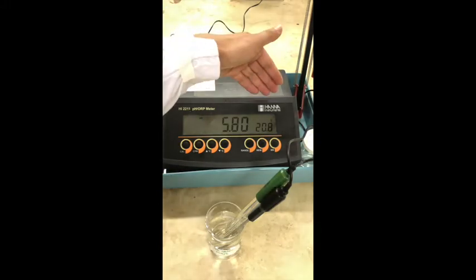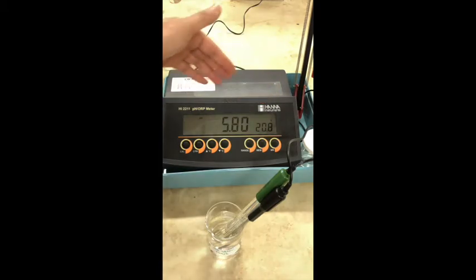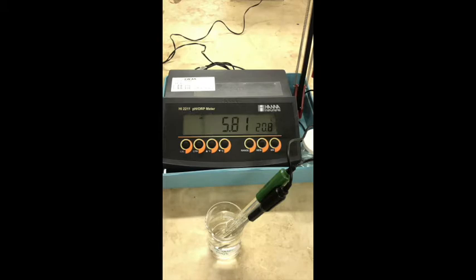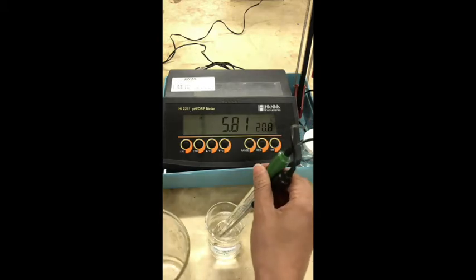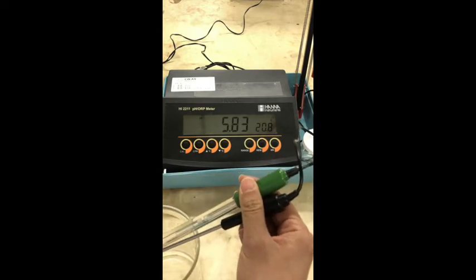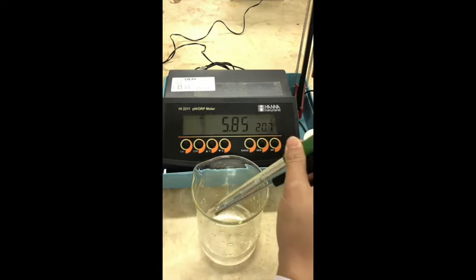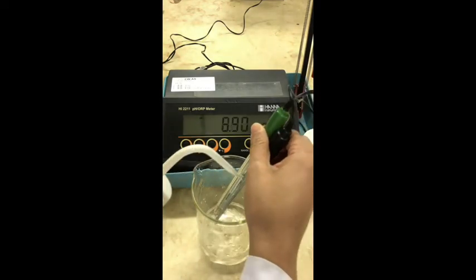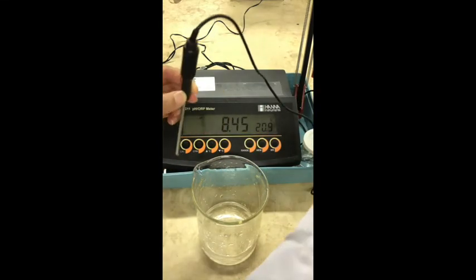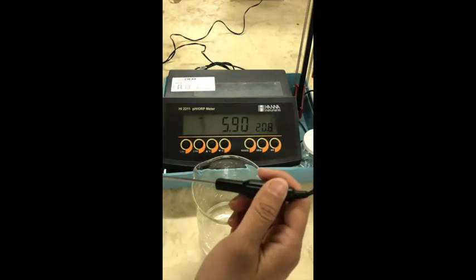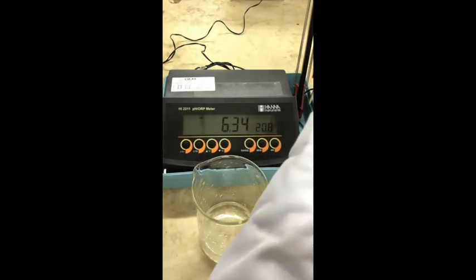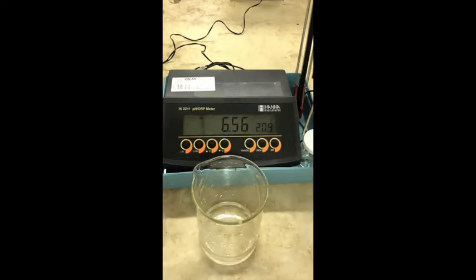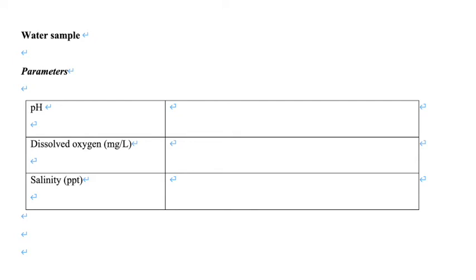And the pH is 5.8, and the temperature of the sample is 20.8 degrees Celsius. After the measurement, remember to rinse the electrode and thermocouple with deionized water. Place the electrode into a bottle containing deionized water. Clean the thermocouple with the lens paper. This is the end of the pH measurement. After the measurement, let's write down our results. The pH of the sample was 5.81 and the temperature of the sample was 20.8 degrees Celsius.